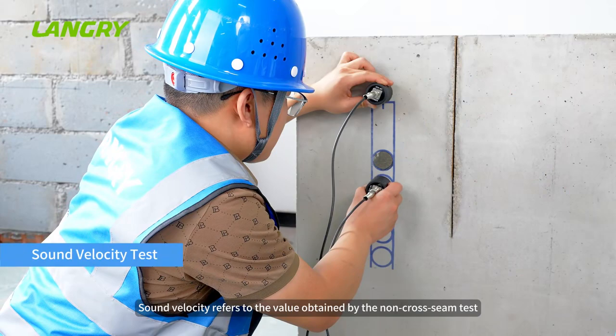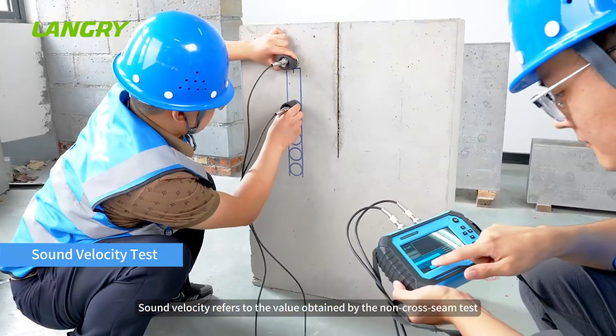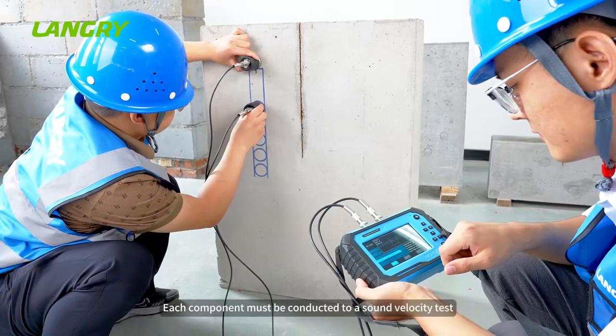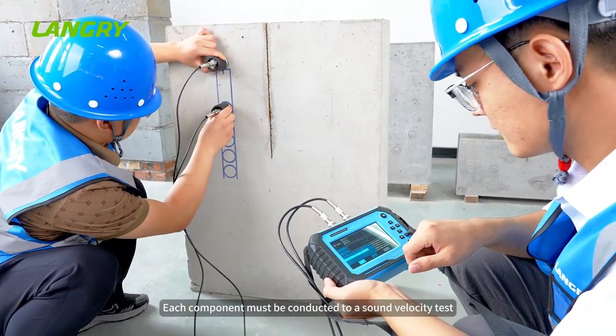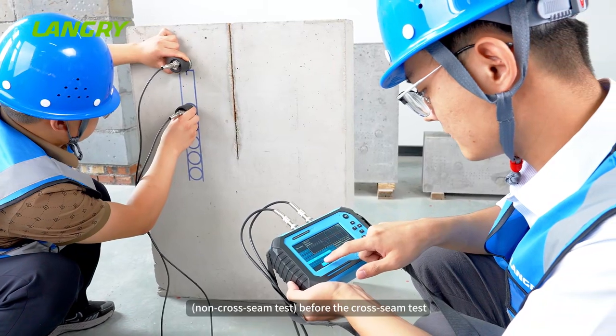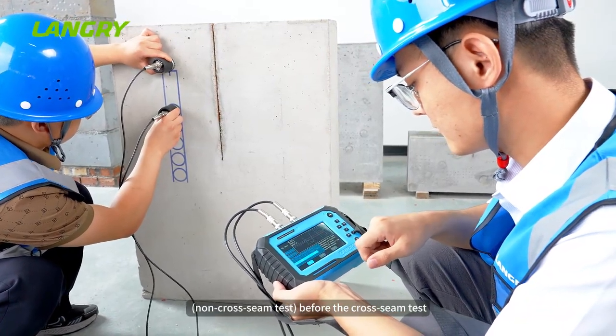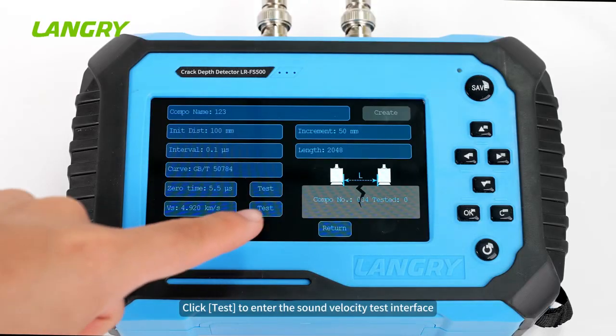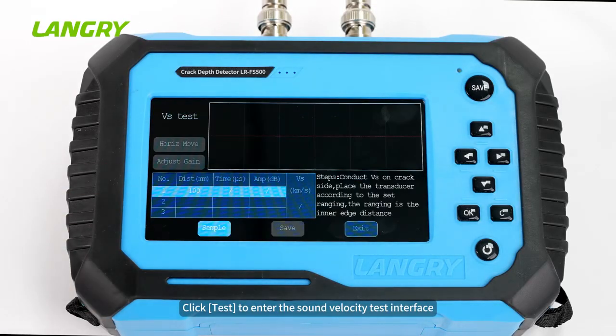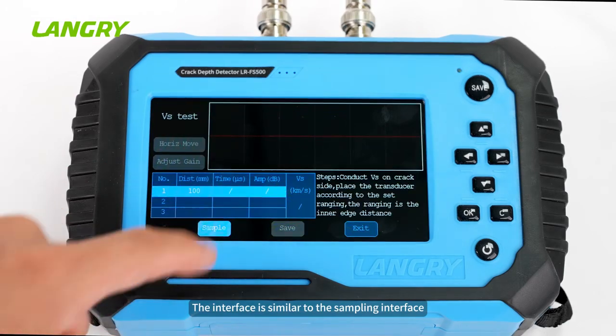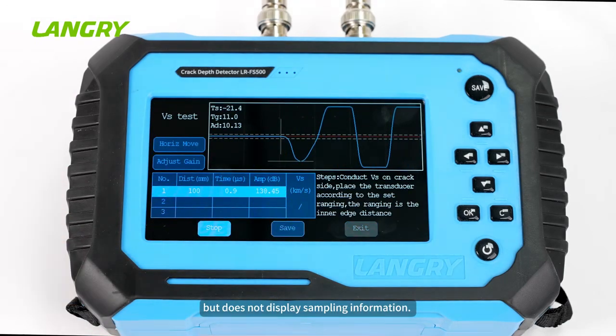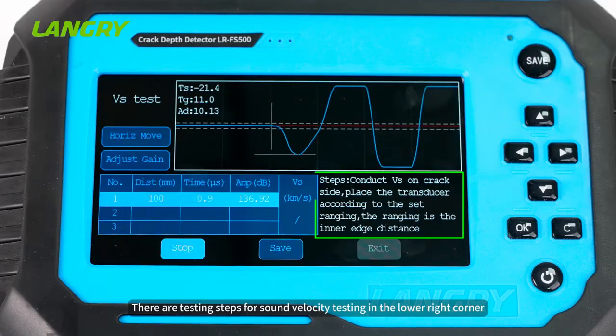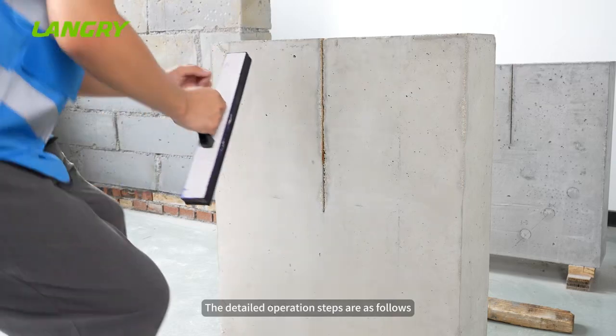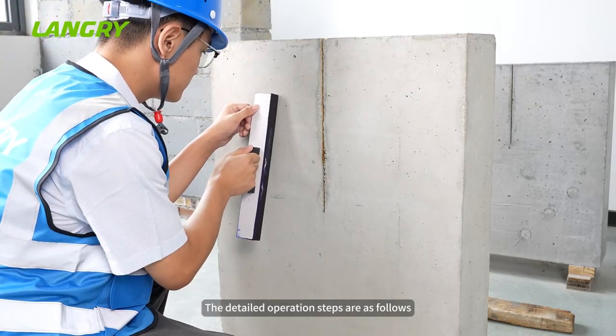Sound velocity refers to the value obtained by the non-cross-seam test. Each component must be subjected to a sound velocity test, the non-cross-seam test, before the cross-seam test. Click Test to enter the sound velocity test interface. The interface is similar to the sampling interface, but does not display sampling information. There are testing steps for sound velocity testing in the lower right corner. The detailed operation steps are as follows.